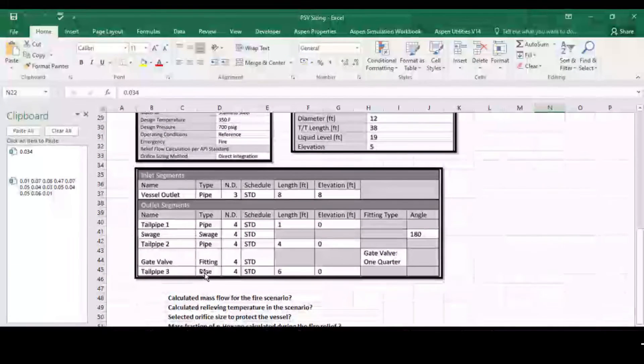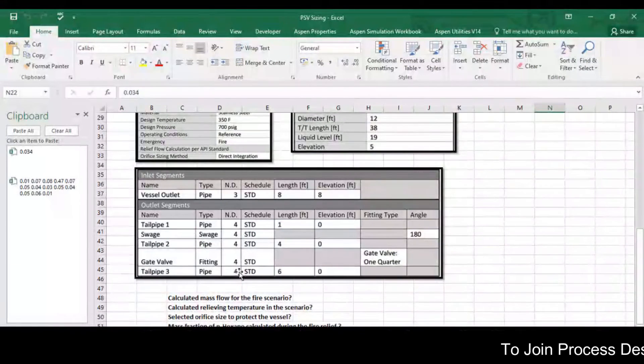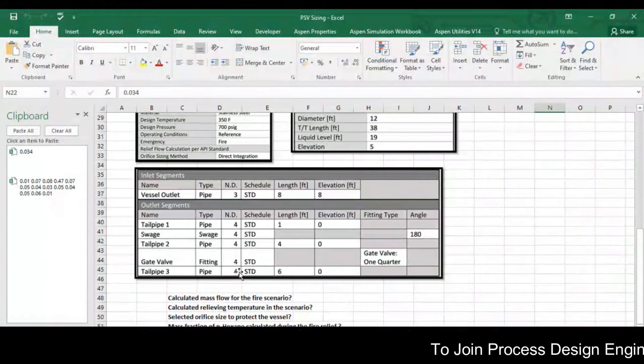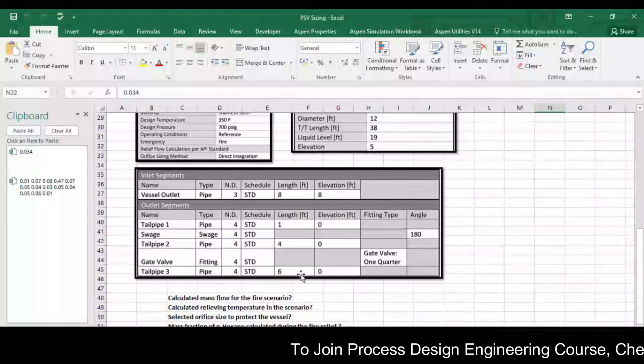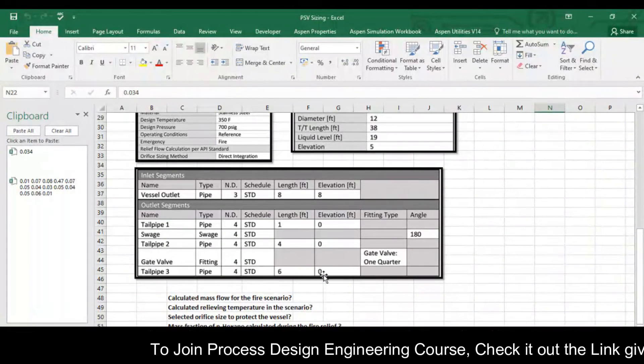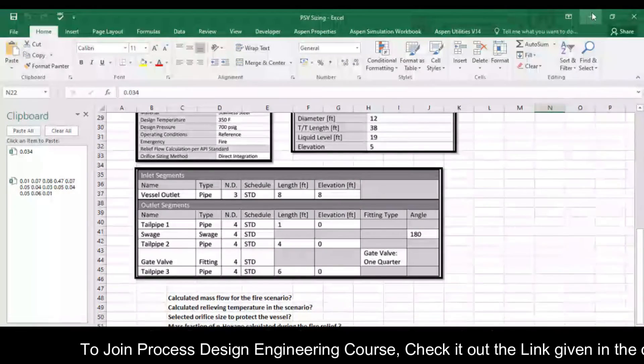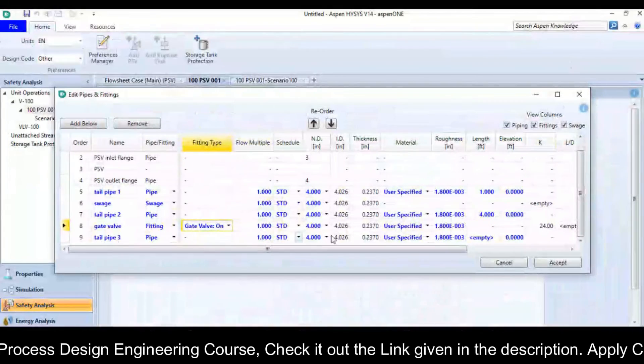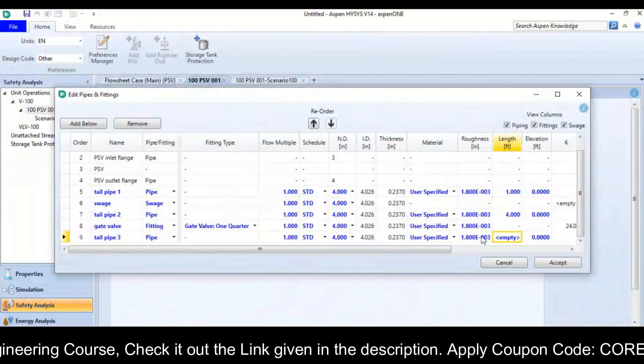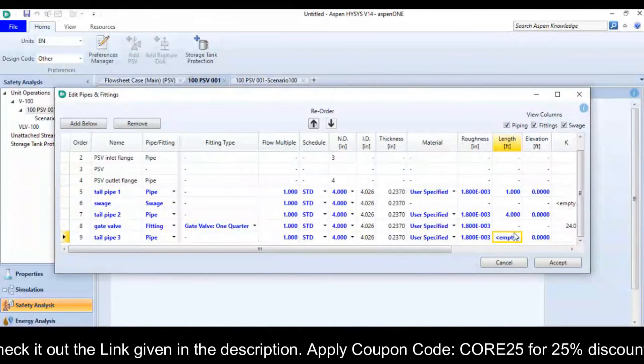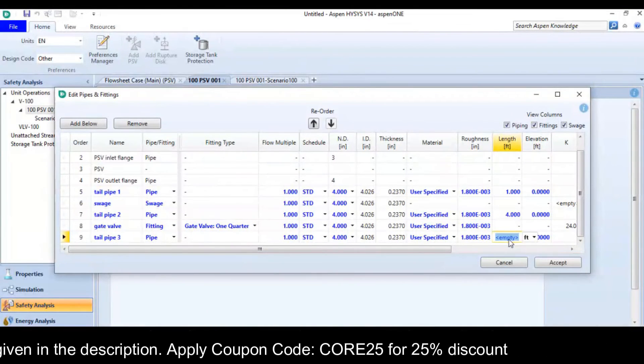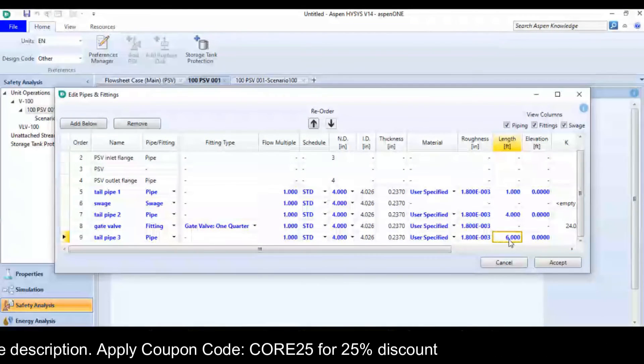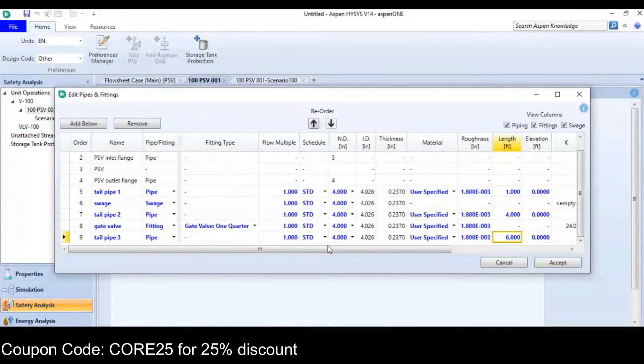Then tailpipe 3, it is 4 inches nominal diameter and 6 feet in length, 0 is the elevation. So it is 6 feet in the length and 0 is the elevation.